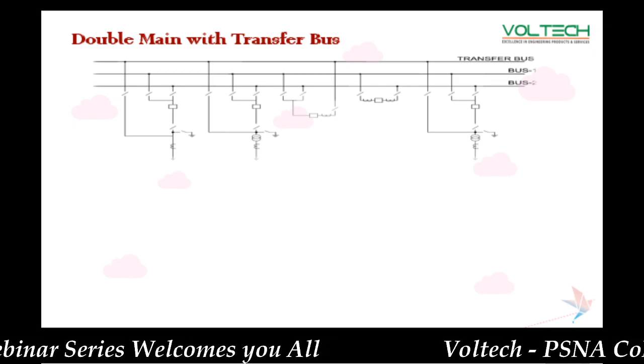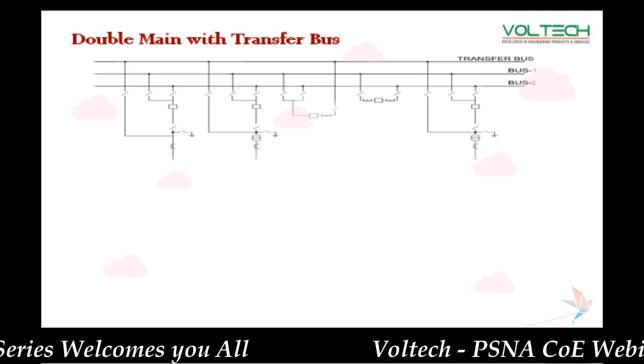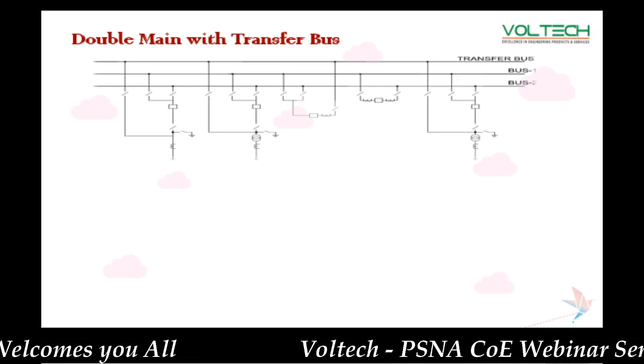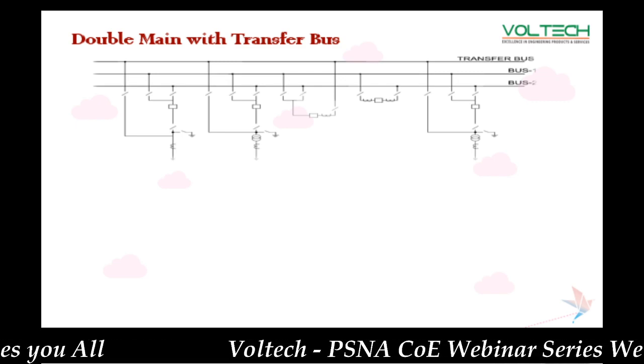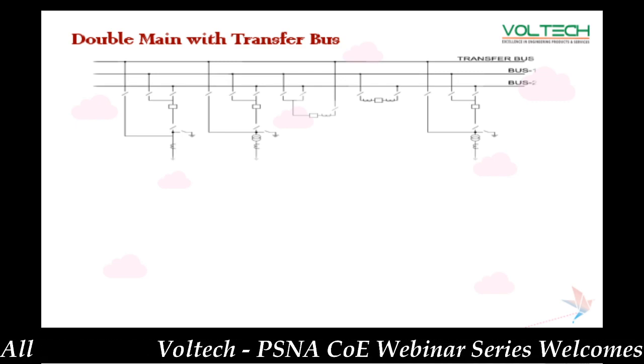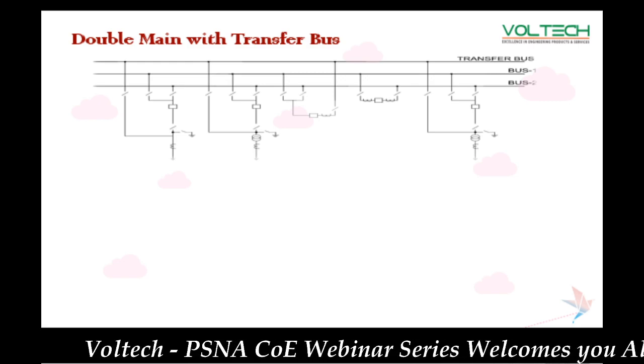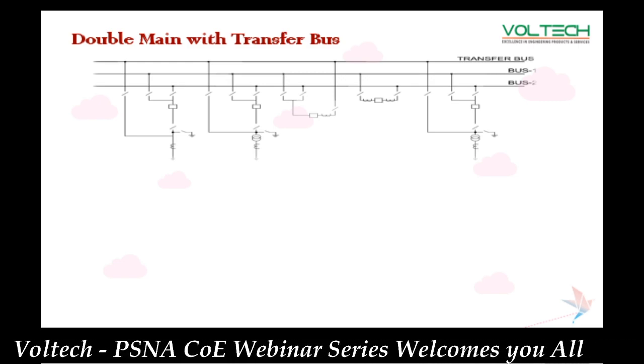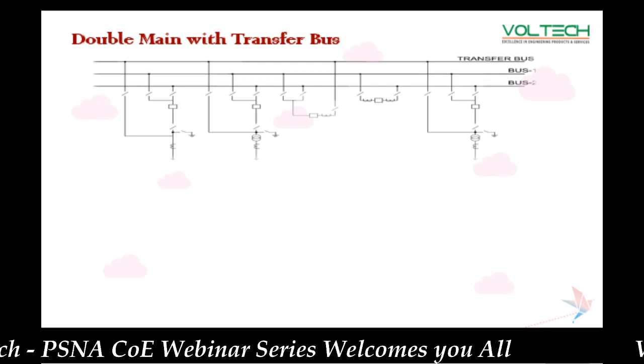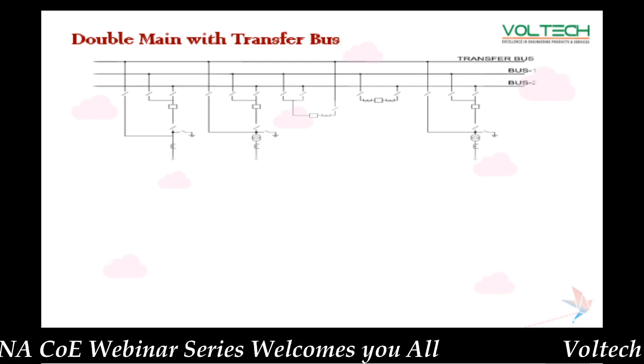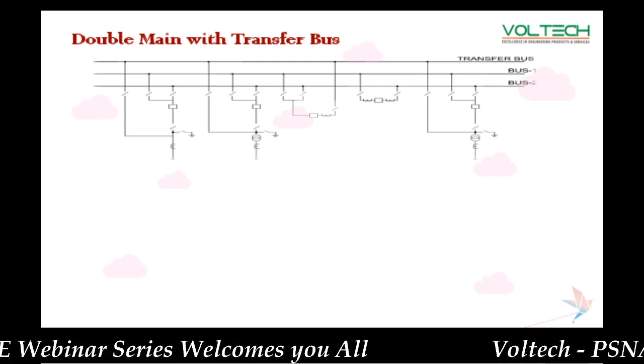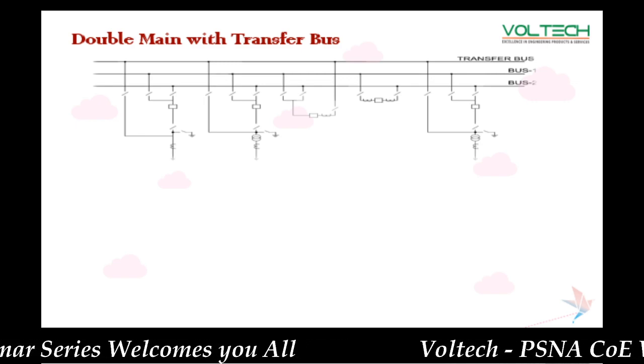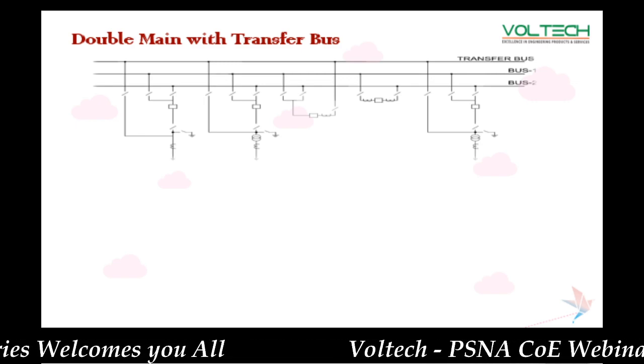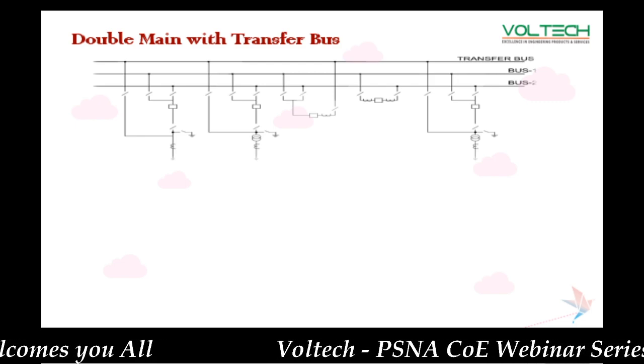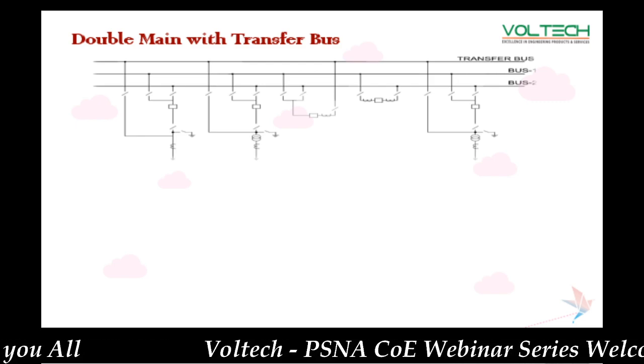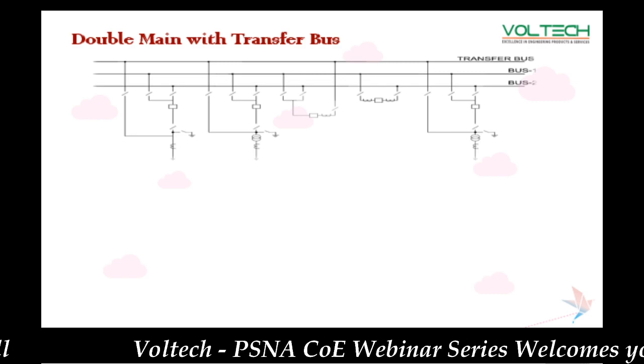This is a double bus with a transfer bus. Before we saw one bus with a transfer bus; here we are using a double bus with a transfer bus. We use two main buses, and here there is a transfer bus. This means we are getting or evacuating power from bus 1 or bus 2.